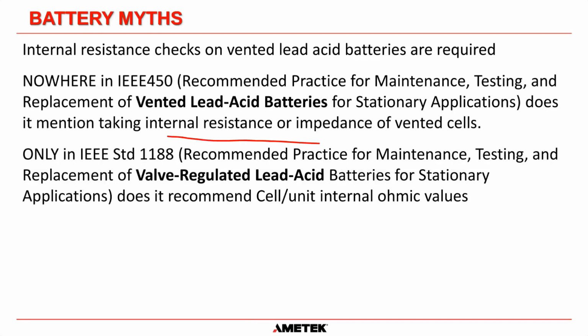Because as long as you can see the plates in a vented lead acid battery, then you can visually see what's going on. You don't need to do internal resistance. Internal resistance is only used in valve regulated lead acid batteries because we can't see what the plates are doing. We can't see inside the battery. So somebody came up with a way to kind of see what was going on inside the lead acid battery without being able to view the plates. And that's where internal resistance measurements came from. They are for valve regulated lead acid batteries only.